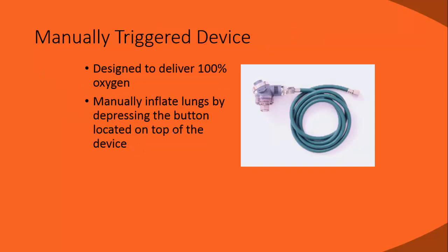So there's manually triggered devices, and these are not automated, which means that obviously here's the oxygen connector. The regulator is our threaded piece that I'm talking about, where once it's open, it's 50 psi being provided, flows through, exits. There is some regulation here by the operator where you push this button. When you push the button, air flows. When you stop pushing the button, air doesn't flow. As simple as that. Now, since this is directly in line on the tank, this is 50 psi and it's 100% O2 because this is likely connected to a tube.